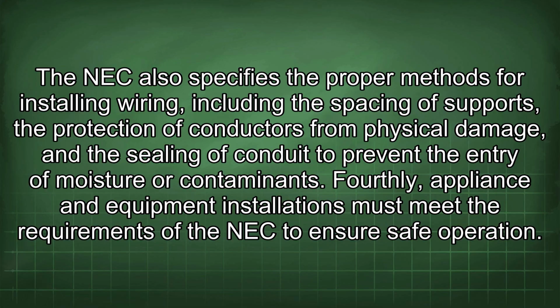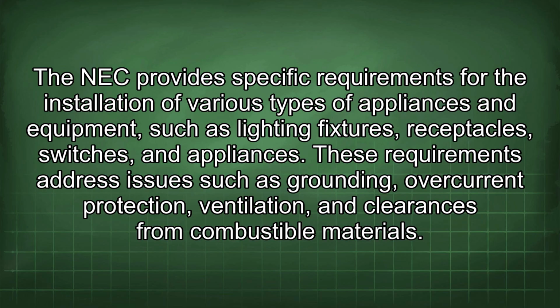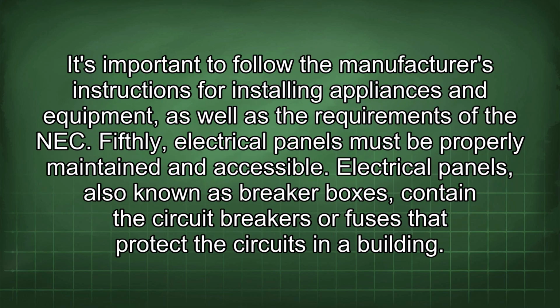Fourthly, appliance and equipment installations must meet the requirements of the NEC to ensure safe operation. The NEC provides specific requirements for the installation of various types of appliances and equipment, such as lighting fixtures, receptacles, switches, and appliances. These requirements address issues such as grounding, overcurrent protection, ventilation, and clearances from combustible materials. It's important to follow the manufacturer's instructions for installing appliances and equipment, as well as the requirements of the NEC.